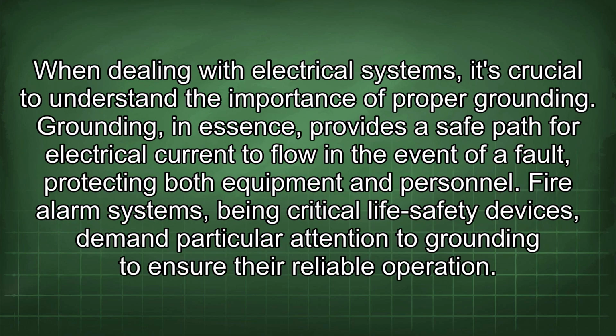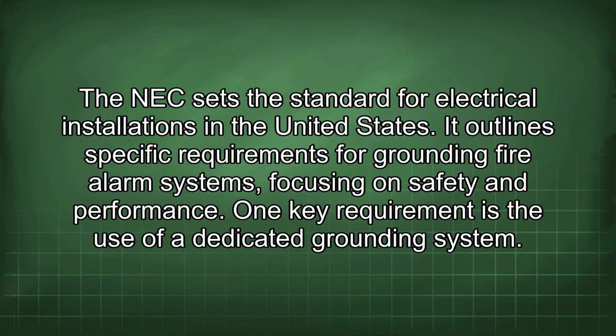When dealing with electrical systems, it's crucial to understand the importance of proper grounding. Grounding, in essence, provides a safe path for electrical current to flow in the event of a fault, protecting both equipment and personnel. Fire alarm systems, being critical life safety devices, demand particular attention to grounding to ensure their reliable operation. The NEC sets the standard for electrical installations in the United States. It outlines specific requirements for grounding fire alarm systems, focusing on safety and performance.